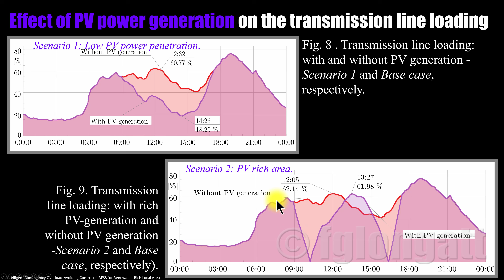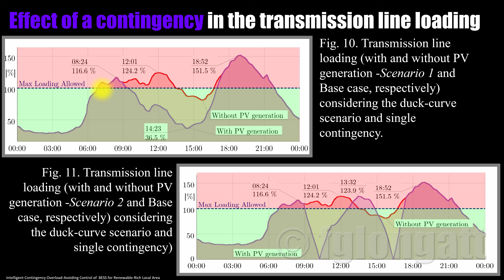Now, what I would like to know is the effect of having a single contingency. In this case, we are tripping the transmission line number 2 and looking into the loading of the transmission line number 1. And what is the situation here? Even for scenario 1 or scenario 2, as you can see, there are several hours where the loading of the transmission line is above the maximum loading allowed, that is 100% for this very specific case. Now, what we want to do is basically use the battery energy storage to solve this problem.